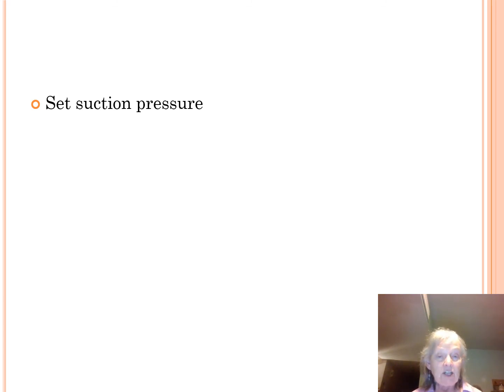We can set our suction pressure, though. Once you set your suction pressure, you're going to go ahead and check at the end of the suction tubing, which is attached to your suction canister, occlude it and see where your pressure goes. If it's greater than a negative 150, you want to bring it back. You can go anywhere between a negative 100 to a negative 150. It's a matter of just what you're comfortable with, okay? So you're going to do that before you put any equipment on the end of it and before you ever start suctioning your patient.